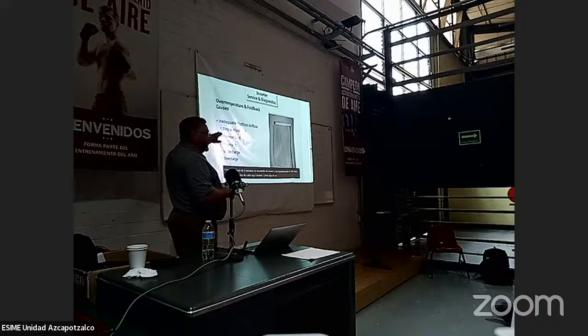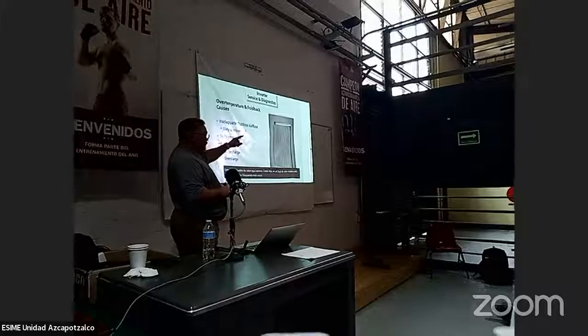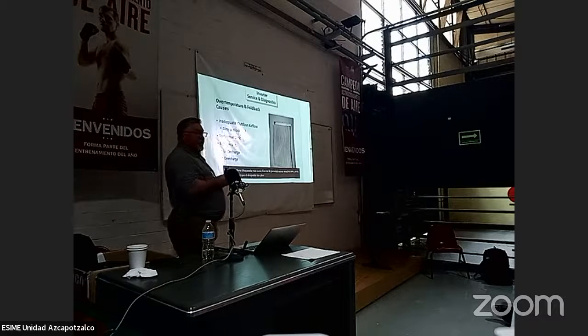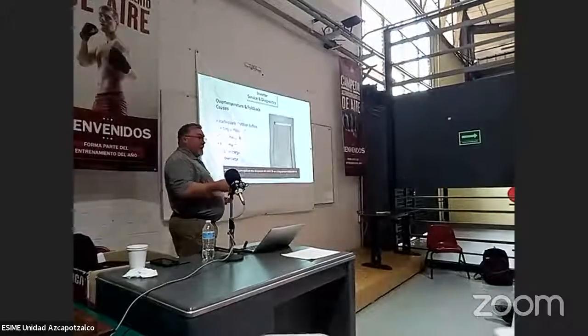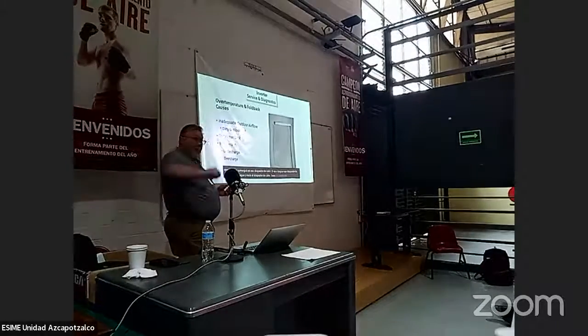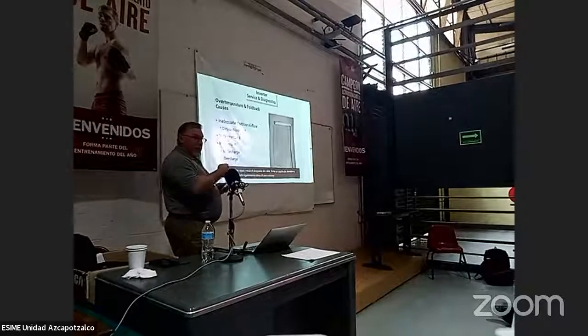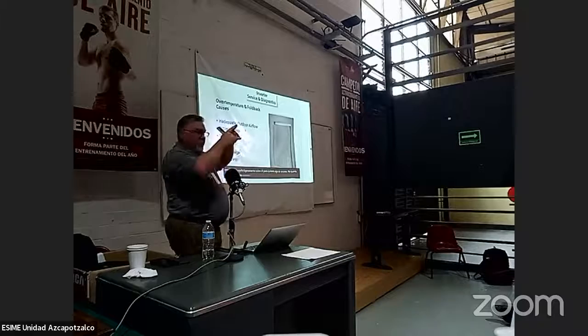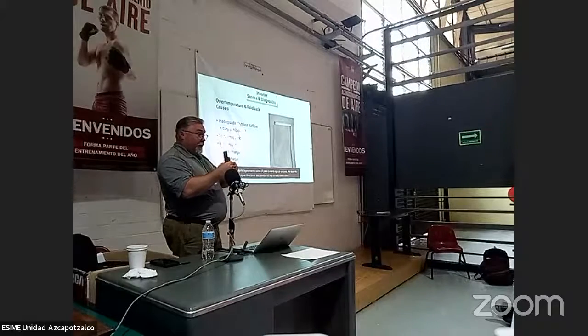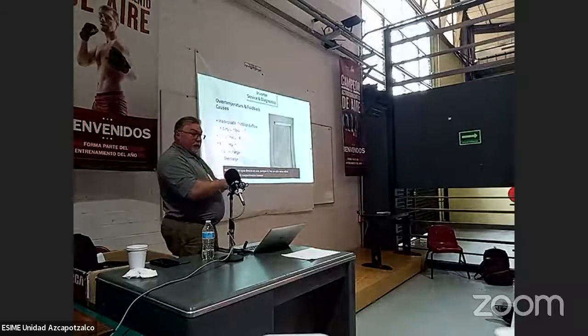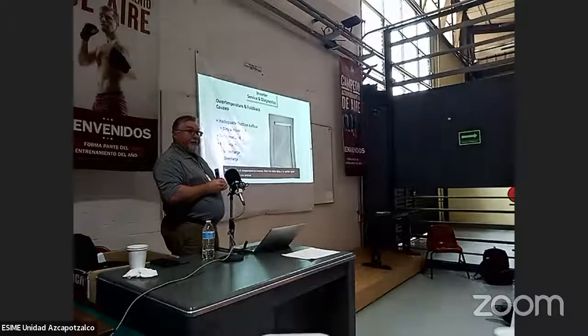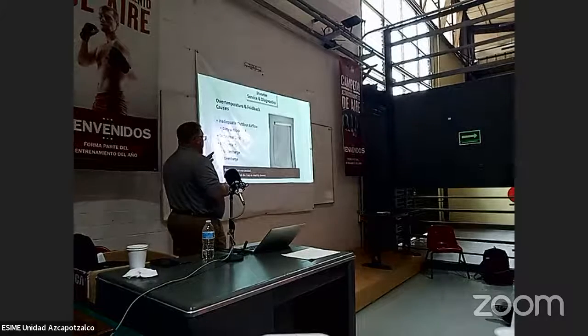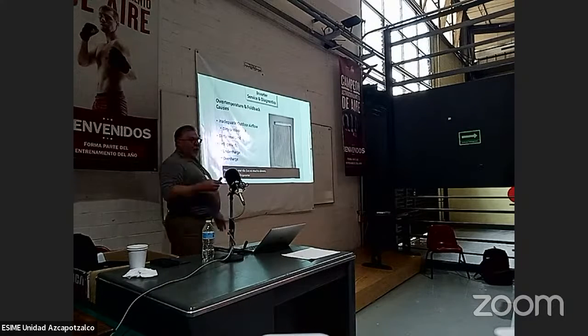This is the heat sink right here. Like I said, inadequate airflow. If you've got a dirty coil that's not going to let you move much air, it's called a heat sink overheat. Dirty heat sink. If it's got junk built up all over, because the coil can get dirty and soak into that heat sink. If you're going to clean that heat sink, don't take water and spray it. Take a wire brush and just brush over it lightly to get anything off of it. You don't want to use direct water spray on that because, yes, there's a seal between it and the inside compartment, but seals fail. And if you spray water right into that unit, you've had a bad day. That's a lot of money. Okay? And also, the refrigerant being undercharged or overcharged can cause the same issues too.